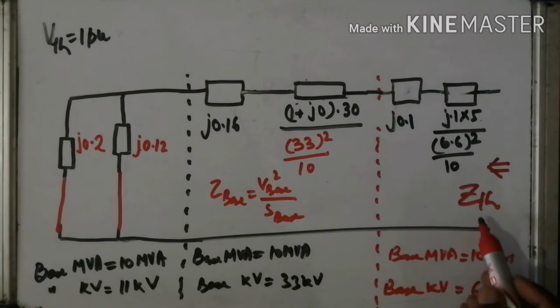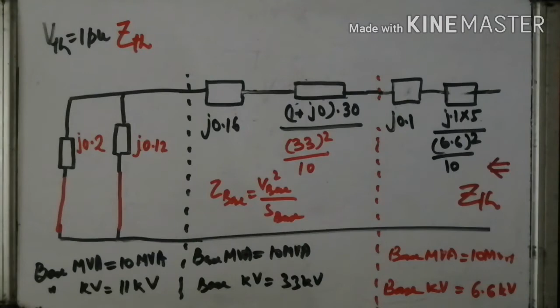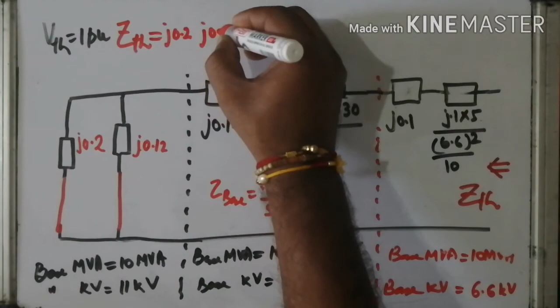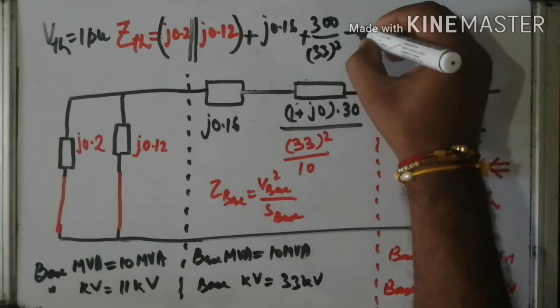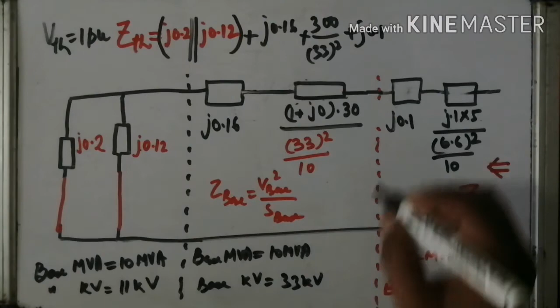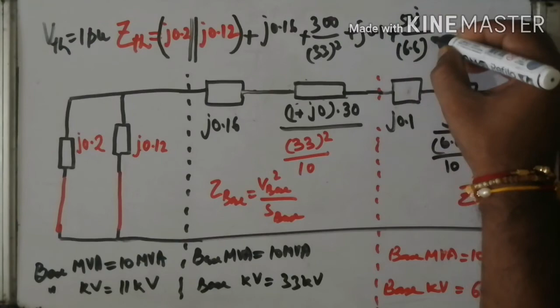Now for the ZTH, these two are connected in parallel, so it is J 0.2, J 0.12. These two are connected in parallel, and with this combination the rest 4 are in series. So this one is J 0.16, this one plus this one, J 0.3, then 30 into 100, 300 divided by square of 33, plus J 0.1, plus this one, 50J divided by 6.6 whole square, right? With the help of this equation we can calculate the value of ZTH.